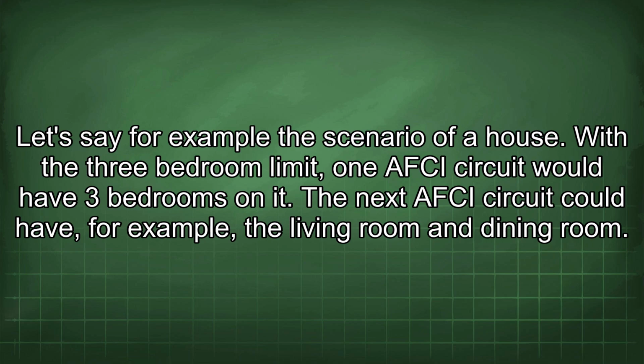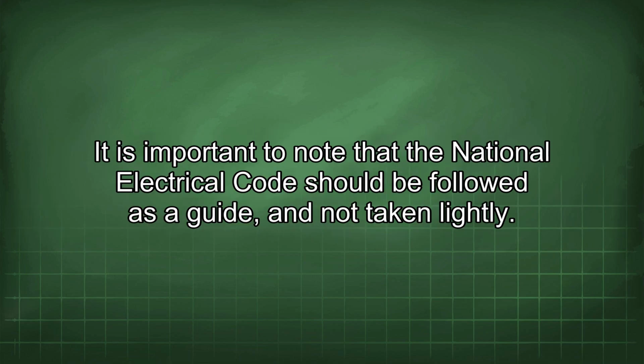Let's say, for example, the scenario of a house. With the 3-bedroom limit, one AFCI circuit would have 3 bedrooms on it. The next AFCI circuit could have, for example, the living room and dining room. It is important to note that the National Electrical Code should be followed as a guide and not taken lightly.